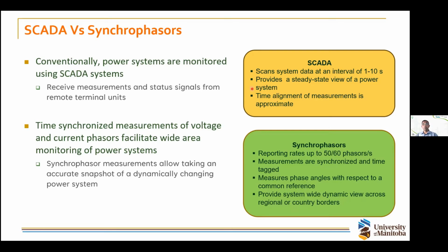But when it comes to synchronized phasor measurement, normally called synchrophasors, that changes the picture completely. These synchronized phasor measurement units have reporting rates of up to 50 or 60 measurements per second, depending on the system frequency. If it's 50 Hertz, you could observe 50 measurements in 1 second, meaning one observation at each cycle.